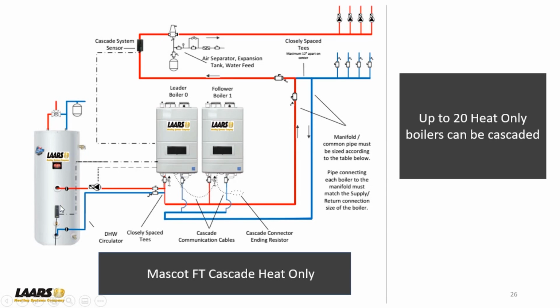You want 180 degrees. But what happens if it's only 50 degrees outside? Your supply temperature to your system might only be 130, whatever you set it at. And now you'll take forever where you may not satisfy that indirect tank. So it should be piped off the primary loop. And what can happen here is we'll go to domestic priority, and this boiler will elevate for domestic priority.